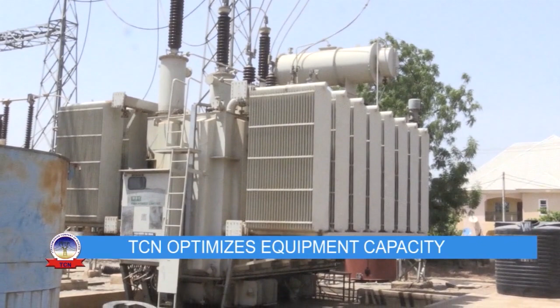The Transmission Company of Nigeria, TCN, has executed a power transformer regeneration activity at the Oshobo substation. What prompted this? When transformers are newly installed, the oil inside the transformer is very new. All their chemical properties are intact. What is the oil in the transformer used for? It's a coolant and it's an insulator.